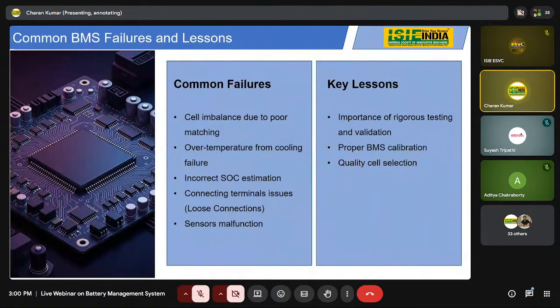Due to poor cell test data or poor sensor data, the BMS fails to calculate the SOC accurately, which also leads to inaccurate SOH calculation. The BMS can also fail due to loose connections, such as those occurring while moving, causing fluctuations from the battery pack, which may also cause BMS failure. To overcome these failures, we must use better, accurate testing data, and tests for cells must be done with calibrated equipment.